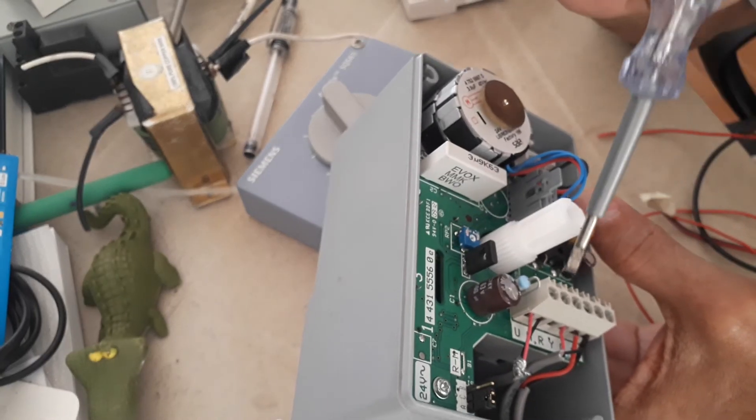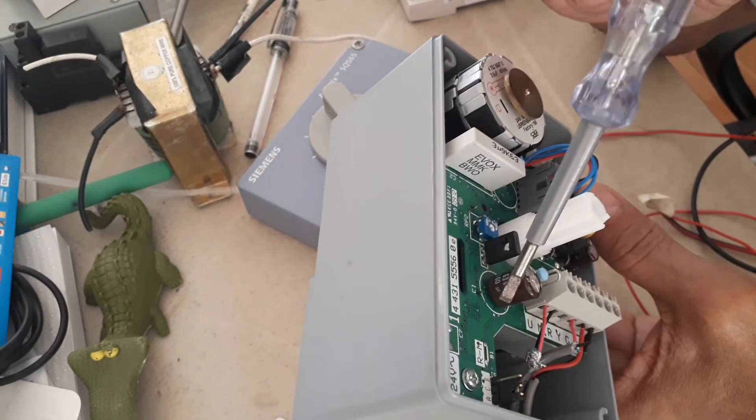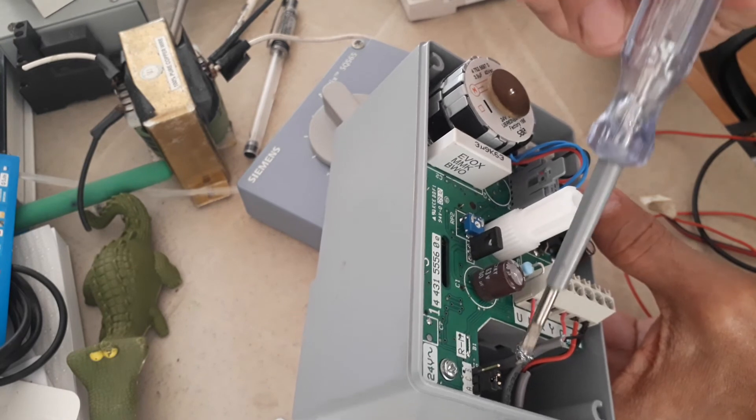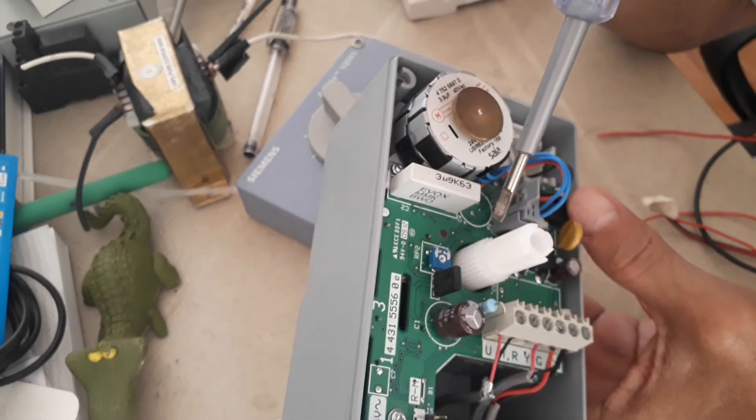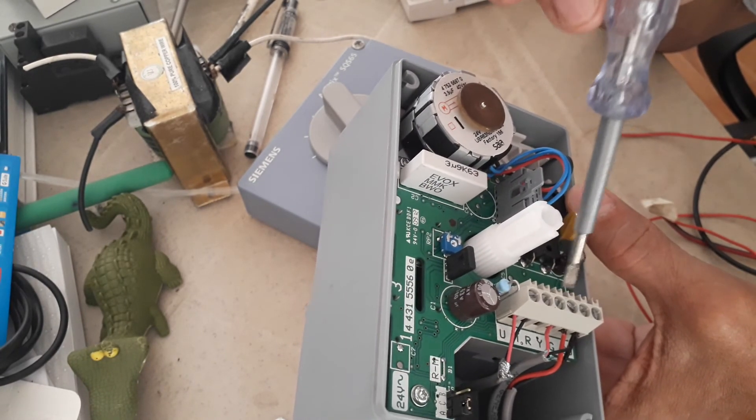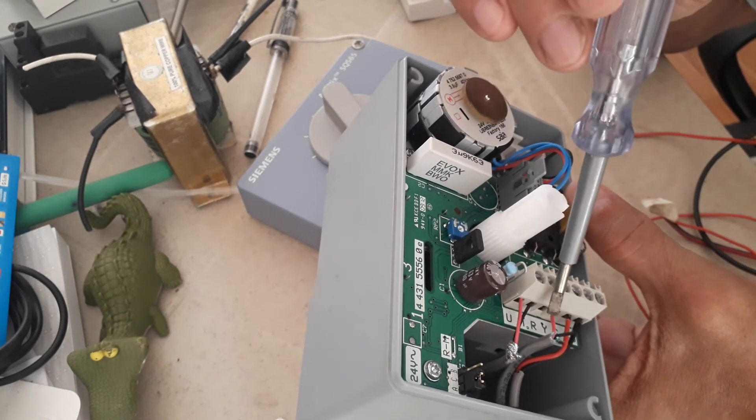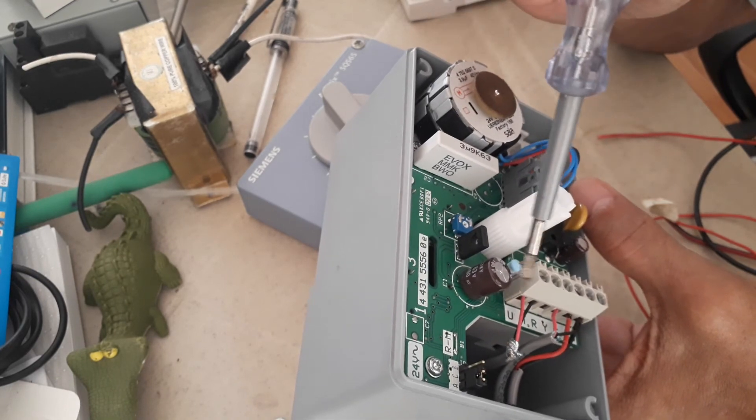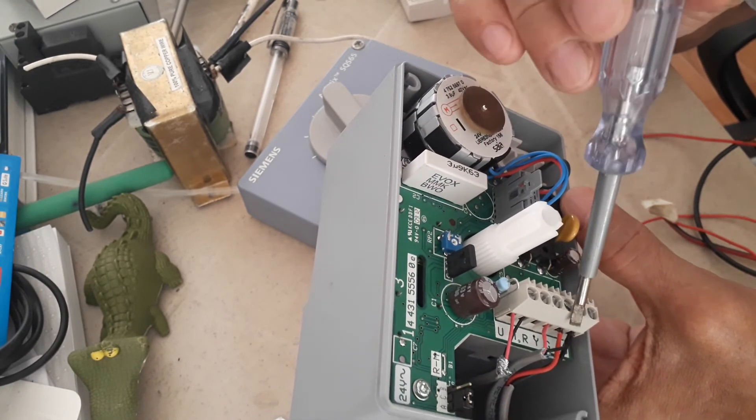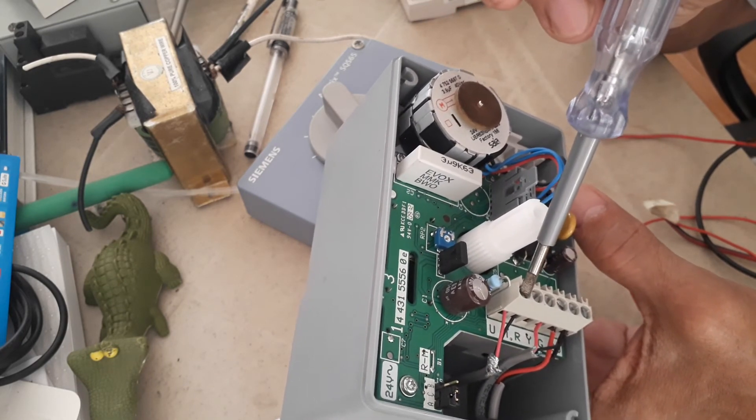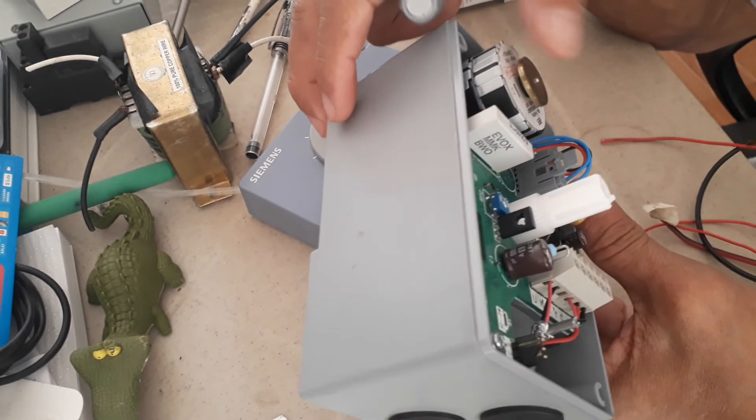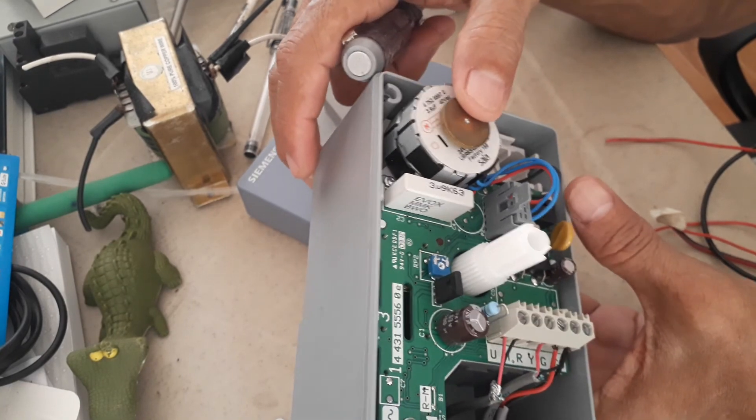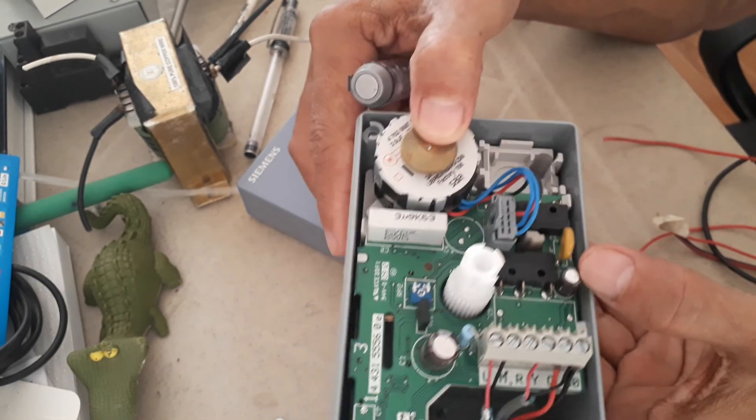There are some switches here which I think you don't need to change because this is factory default. If this valve actuator can receive 0 to 20 milliamps, then you have to change the dip switch setting here. But this one is already set to 0 to 10 volts control signal and 0 to 10 volts feedback signal. These are the components inside. I don't think you need to do some configuration. All you need to do is follow the wiring instruction.